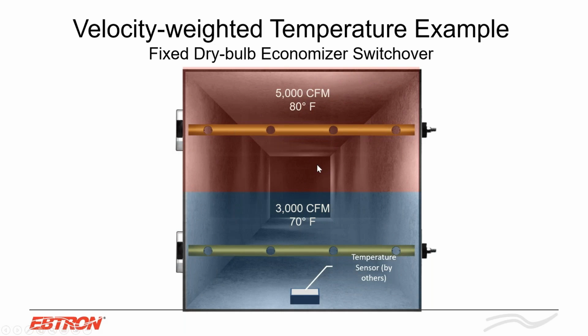Let's say we're doing a dry bulb economizer strategy, and let's say, your contractor, the sensor that you buy, you're going to install it at the bottom of the duct. It doesn't matter, but for this example, let's say the bottom of the duct. And we have 5,000 CFM on the top of the duct. We have some stratification, and we have 3,000 CFM on the bottom of the duct. And you'll notice 80 degrees on the top of the duct and 70 on the bottom.